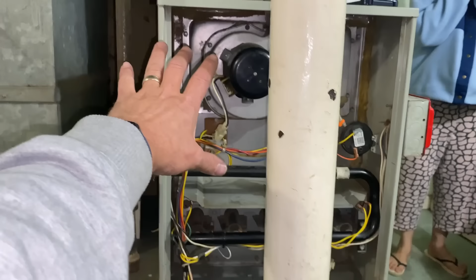This is a rollout switch. So if flame was here, it's going to turn off the furnace. There's another one right there as well. We have a hot surface igniter at the end of these 2 lines, and then we have our flame sensor there. That's all the components of the ignition system. Here on the bottom half, we have our door switch, right? So if I push this in and the switch is on, it'll do something.